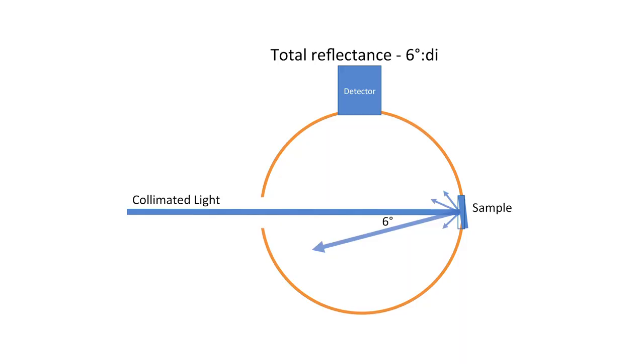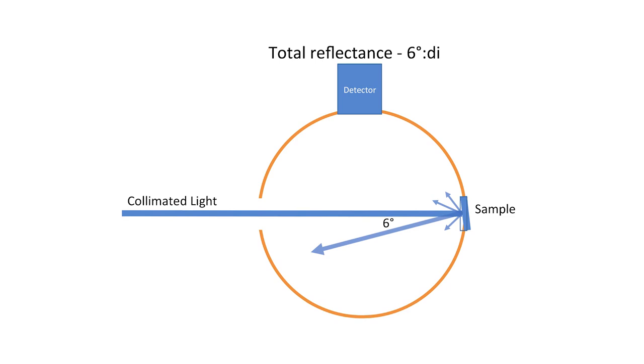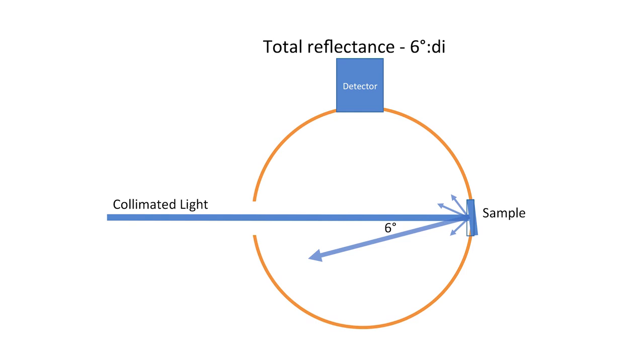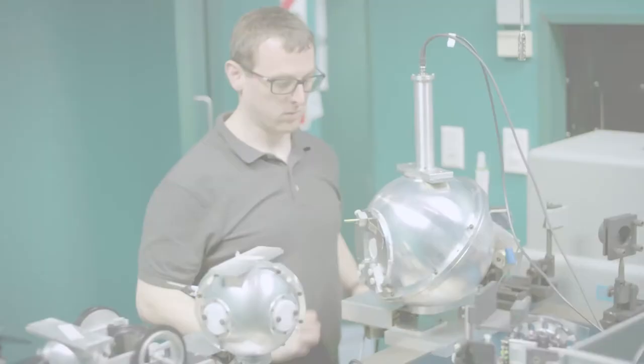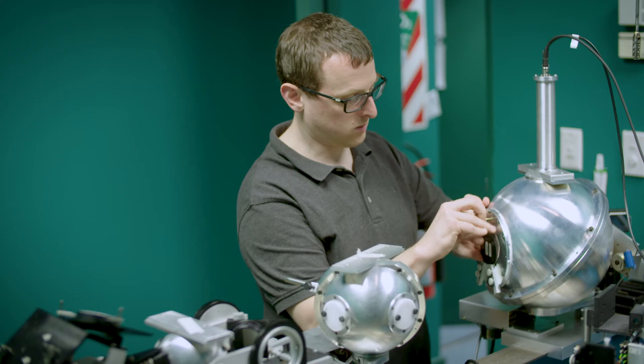We press the sample against the port on a sphere lined with highly reflecting white material and illuminate the sample at six degrees from normal. All of the light that is reflected off the sample whether diffusely or in the specular direction is captured by the sphere and collected by a detector mounted on the outside of the sphere looking in. This measurement is also primarily about colour and is largely insensitive to the texture of the surface.